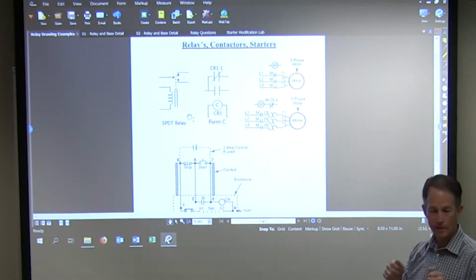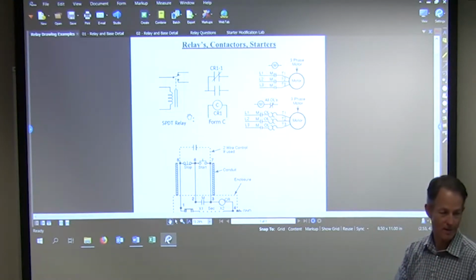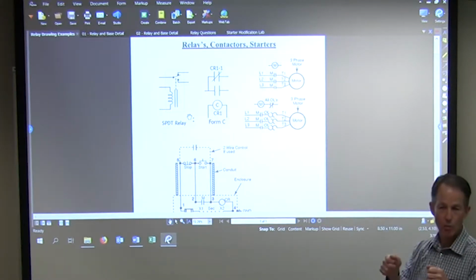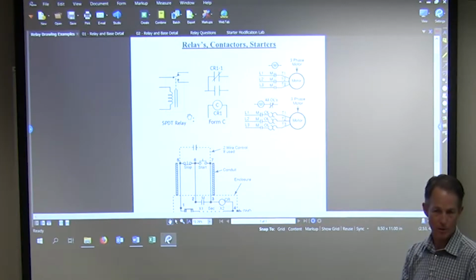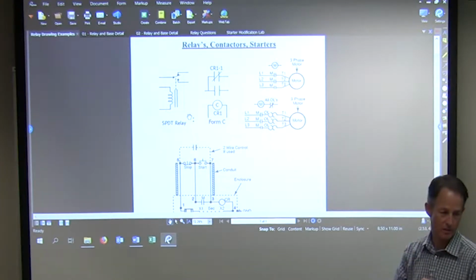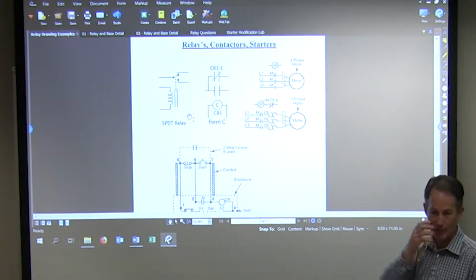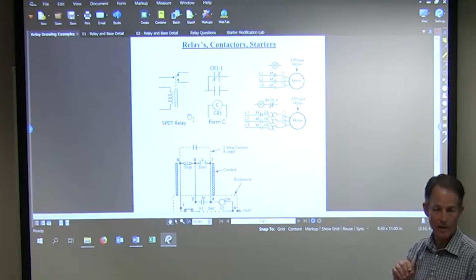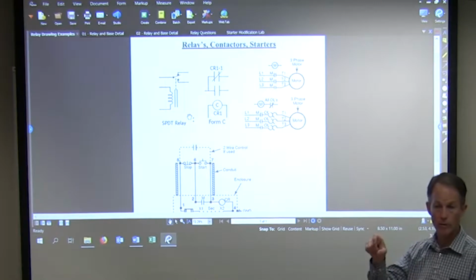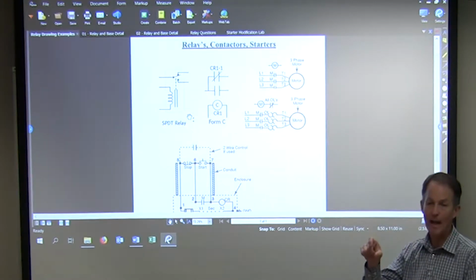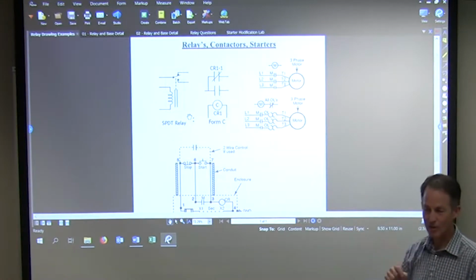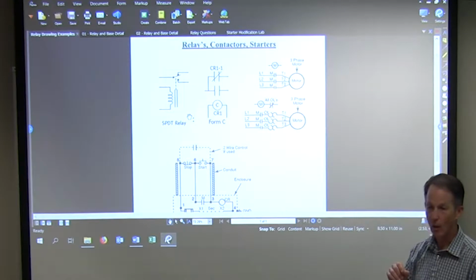If the meter measures potential, the load will have a voltage drop across it. Okay. Right. So if it's not powered, you will measure a short with an ohm meter, or a very low amount of resistance, right? It will be 15 ohms, 20 ohms, something like that. It's a very low amount of resistance. And the resistance in that coil is dependent on the voltage that's applied to it, right? If we put a 24 volt coil in a 120 volt circuit, what happens? Doesn't last long, right? Usually the smoke goes out pretty quick. Okay, or vice versa. If I put a 120 volt coil in a 24 volt circuit, what happens?